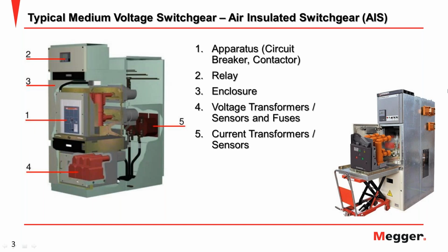Okay, let's move to the next slide. I will give you a little overview about the medium voltage switchgear. This is a sample of the air insulated switchgear, or AIS, very common. You can see it as MV switchgear, mostly at distribution voltage level. Before I talk about the circuit breaker and all the testing of the MV breaker, let me introduce this again. So here you will understand where the location of the breaker itself is on the MV switchgear. Because in the electric power system, switchgear is a combination of electrical devices like a breaker, switch, or fuse to protect and isolate the electrical equipment.